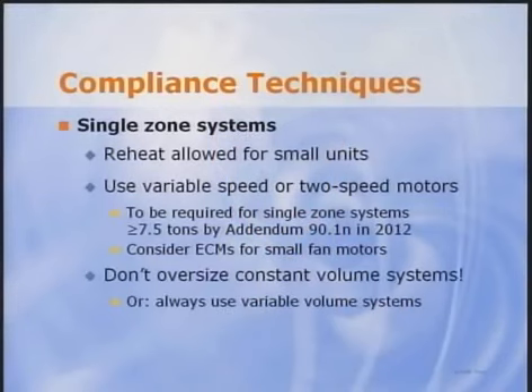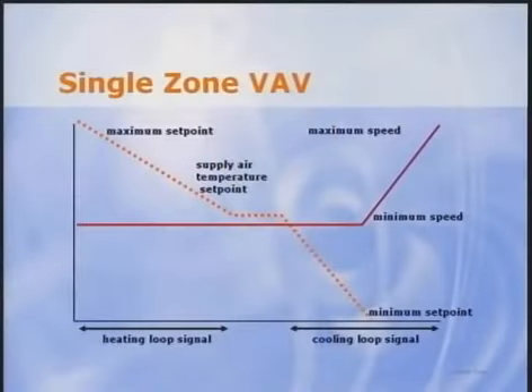One last reminder, don't oversize constant volume systems. Not only does this increase fan energy, but it results in poor dehumidification. Another choice, simply don't use constant volume systems. Again, the falling cost of ECMs and variable speed drives makes VAV an option for almost all chilled water and variable capacity systems. This figure shows how variable speed motors can be controlled on single-zone variable volume systems.